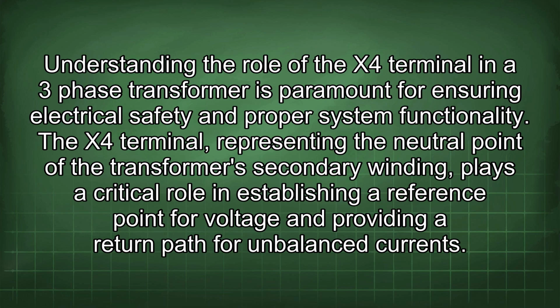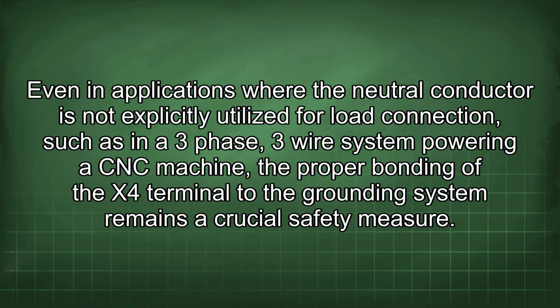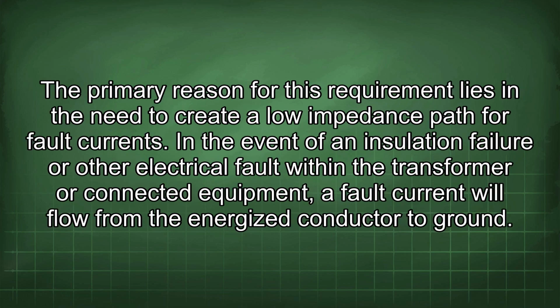Understanding the role of the X4 terminal in a three-phase transformer is paramount for ensuring electrical safety and proper system functionality. The X4 terminal, representing the neutral point of the transformer's secondary winding, plays a critical role in establishing a reference point for voltage and providing a return path for unbalanced currents. Even in applications where the neutral conductor is not explicitly utilized for load connection, such as in a three-phase, three-wire system powering a CNC machine, the proper bonding of the X4 terminal to the grounding system remains a crucial safety measure. The primary reason for this requirement lies in the need to create a low impedance path for fault currents.